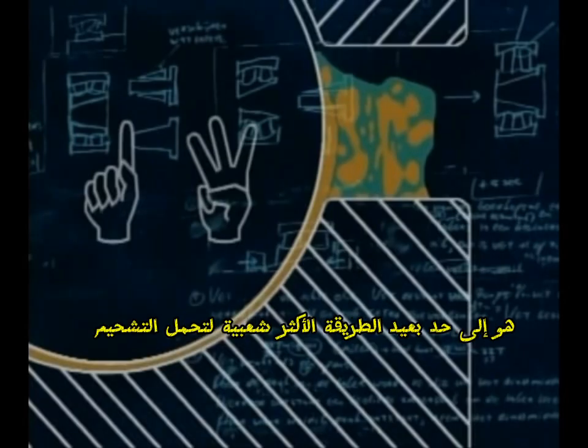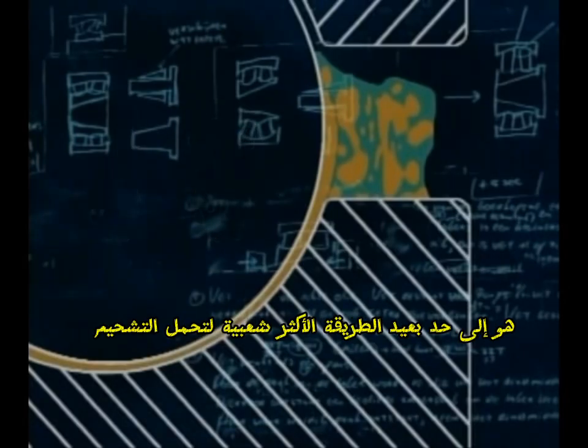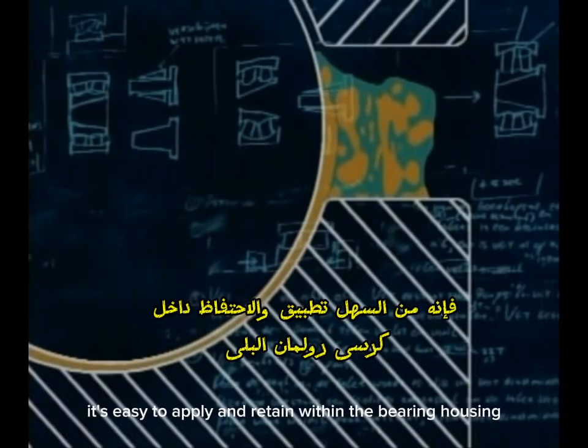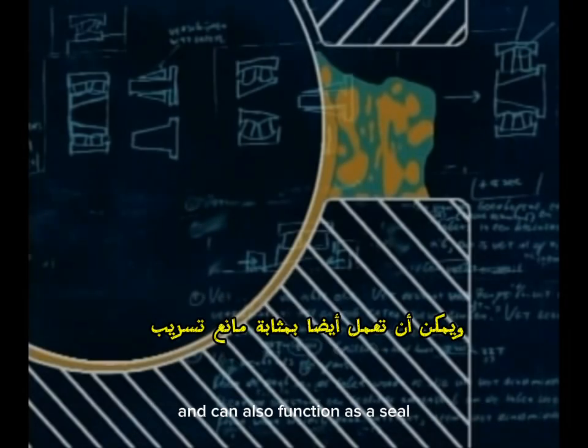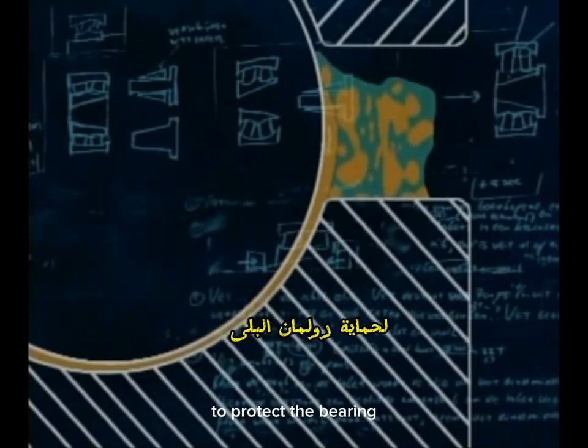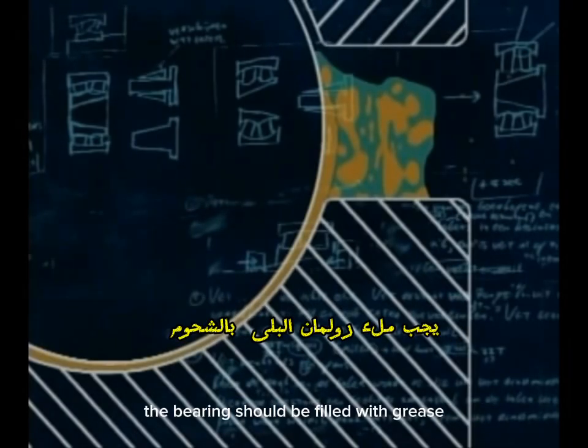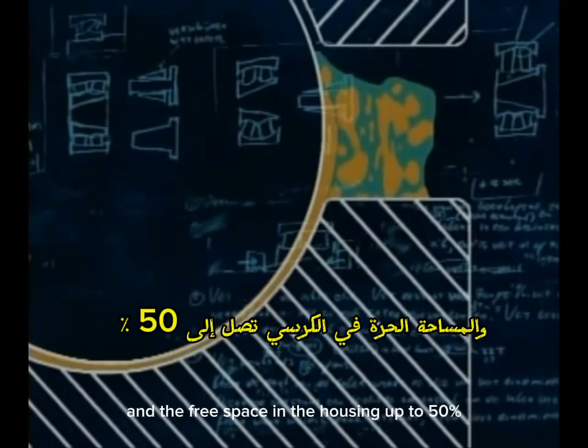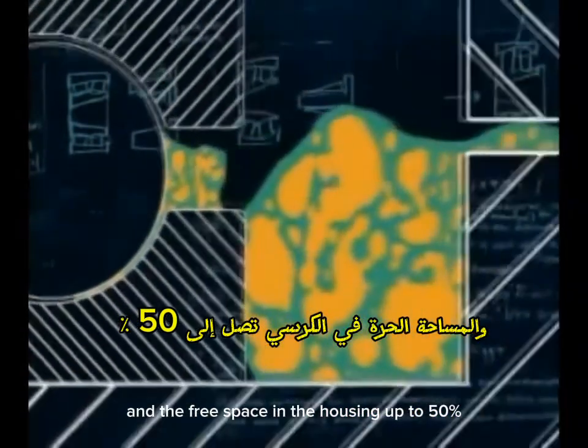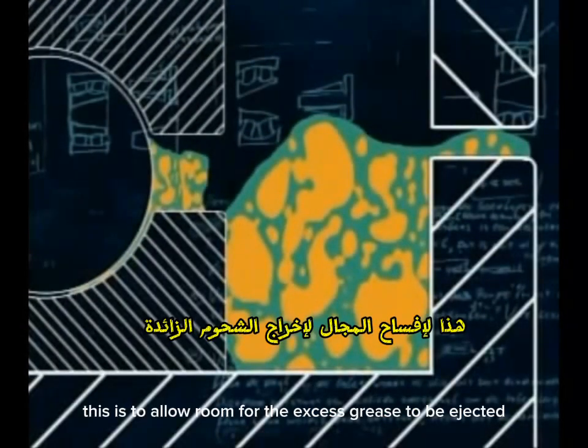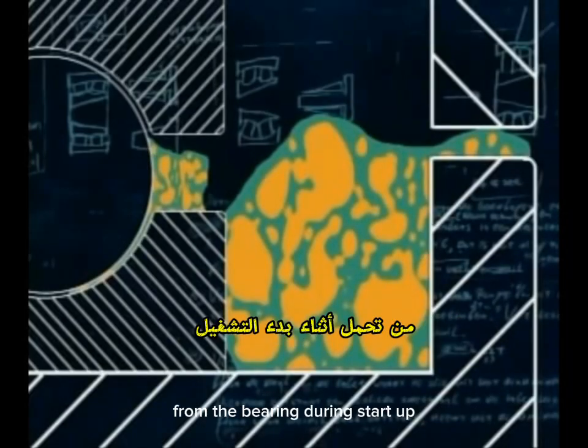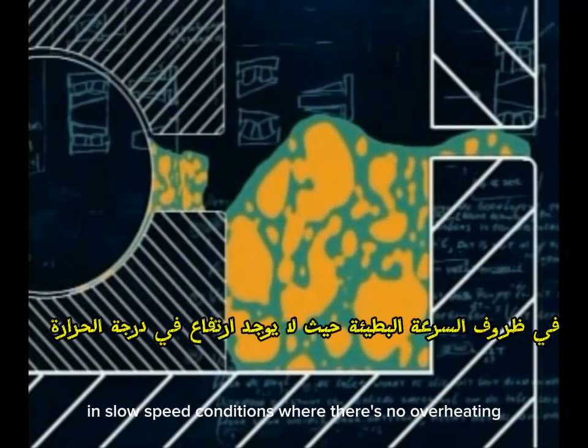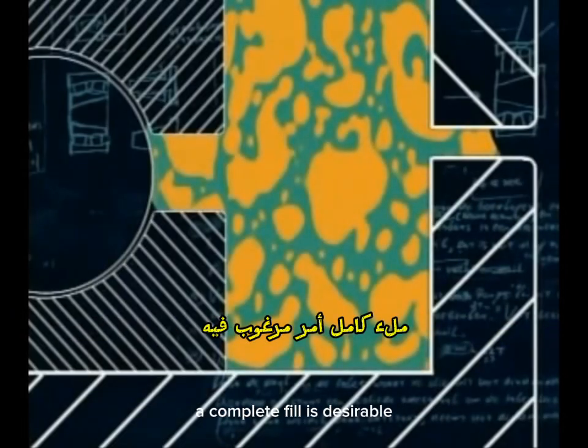Grease is by far the most popular method for bearing lubrication. It's easy to apply and retain within the bearing housing, and can also function as a seal to protect the bearing. The bearing should be filled with grease and the free space in the housing up to 50%. This is to allow room for the excess grease to be ejected from the bearing during startup. In slow speed conditions where there's no overheating, a complete fill is desirable.